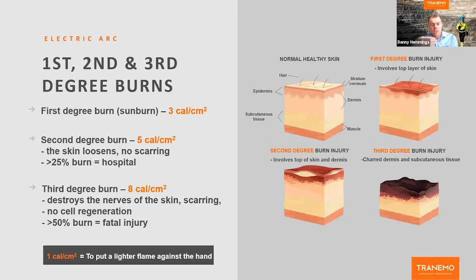It then doesn't need to rise too much to start to have second and consequently third degree burns, which become much more of an issue for the body to deal with. With a second degree burn, we look loosely at an incident energy around 5 calories per centimetre squared. In that, there will be damage to the skin, minimal or no scarring, and in an industrial environment or an environment where the body has been subjected to the incident energy, we generally look at 25% being the level above which someone would require some kind of hospital or medical treatment. Generally, with a second degree burn, if the percentage on the body is lower than 25%, then the skin will regenerate and there shouldn't be any permanent scarring.